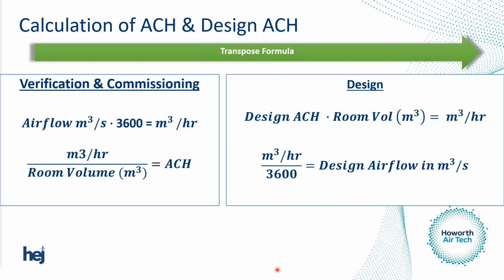And then just for the people that may not be au fait with where I'm getting these calculations and figures from, this is a formula that we use to work out an air change rate. Basically take the airflow in meters cubed per second, multiply it by 3,600 seconds in an hour, turn it to meters cubed per hour, divide that by the room volume, and that gives the air change rate. And then we can transpose that formula to work from the office as a designer. We'll take a design air change rate from HTM 03, and we'll take the room volume. So we have two constants. That'll give us meters cubed per hour.